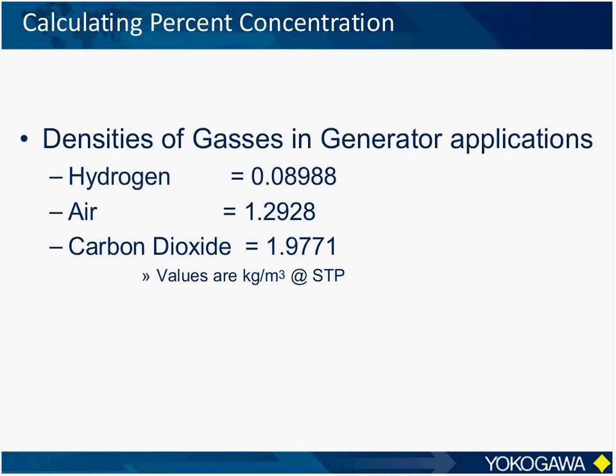Now, the three gases involved in generator applications, there's three of them, each of them with their own distinctive density. Hydrogen, which flows to the generator to cool in normal operation. During that normal operation, air is a contaminant due to leakage. Also, there's carbon dioxide, which is used to purge the generator of hydrogen when the generator is shut down for maintenance activities. Once the generator is purged of hydrogen, the carbon dioxide is then purged out with air, so the environment is safe for technicians.